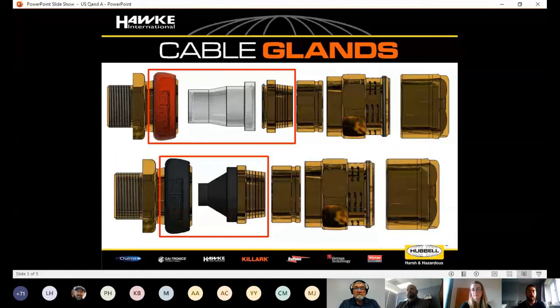Now, for us to be able to do this, we had to work closer with our certification bodies to ensure that we could mark the product correctly. The deciding factor is the colour of boot that is installed on the gland when it's finished. So the marking states 501-453 universal black and ICG 653 universal red, and that gives the ability to mark one product with 2 different uses, and gives us the versatility of two products within one potentially.